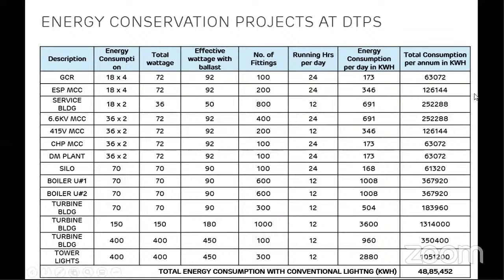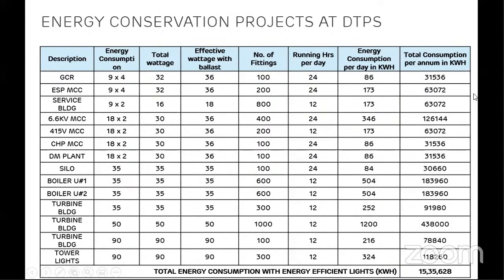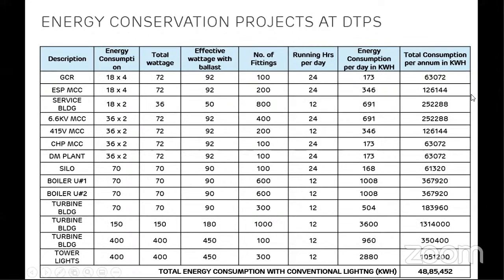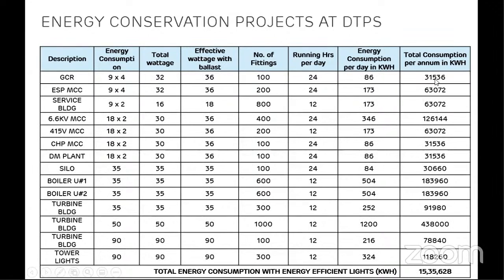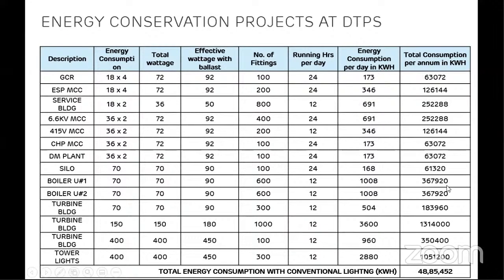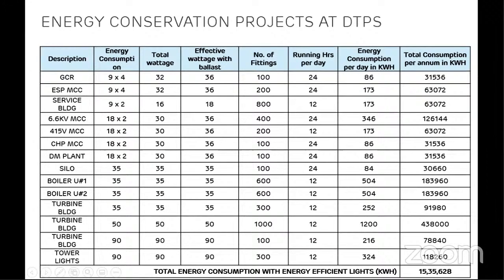Now we replaced these tube lights with LED lamps. The 18 watt tube light was replaced with a 9 watt LED. The power consumption was reduced from 63,000 kWh to 31,000, almost half. So for each building, if you keep on adding, the power consumption reduced from 48 lakh units to 15 lakh units. So that much saving we have gained. Almost half, or 50%, of the power is saved. More than 50% power is saved after installing LED lamps instead of CFL or tube lights.